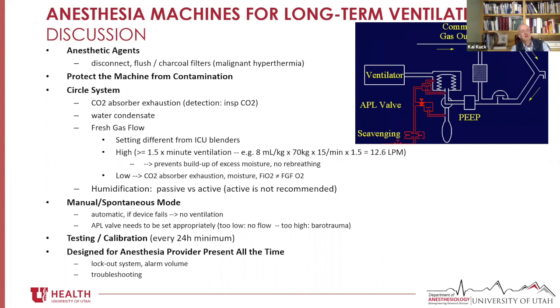And then another important one: because if you have low fresh gas flow, you're recirculating the air, the oxygen concentration that's going into the circuit is not exactly the same as what the patient sees. It's often higher than what the patient is seeing. The patient is seeing a lower oxygen concentration than what you feed into the circuit, because they're consuming oxygen, and you need to keep that in mind when you dial it in. What else? We talked about the manual spontaneous mode. Oh, that's right.